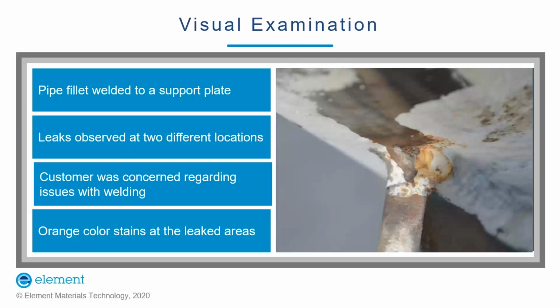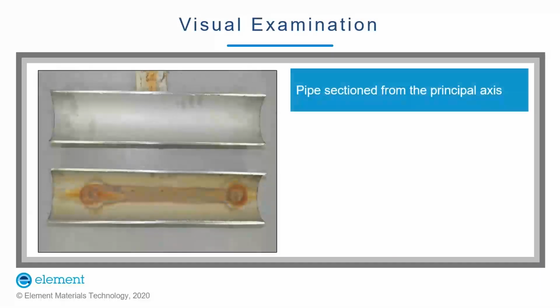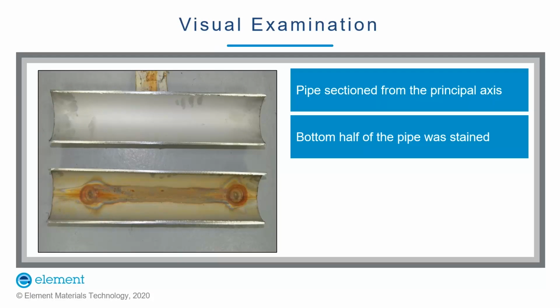At the leak location, orange colored stains were observed. As leakage was found on the outside of the pipe, we wanted to see the internal condition of the pipe, and that is the reason the pipe was sectioned into 2 halves. The picture shows the inner views of the pipe, which revealed the top half of the pipe to have a bright and shiny appearance, which is a sign of no stagnant water. The bottom half of the pipe was stained. This indicated that it may have been exposed to the hydro test water, which was not properly dried after the hydro test.